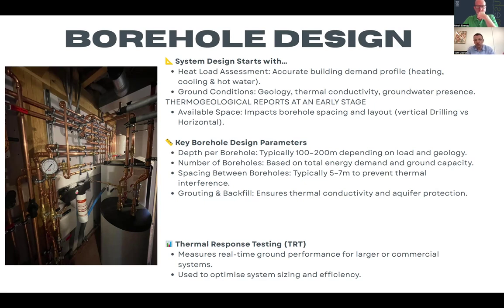That depends on the size of the project. You might drill one borehole up to 50 or more. We've been working on projects where we are looking at 300 boreholes. So it varies depending on the demand of the property. What's important is also knowing what kind of grout and backfill you are going to use in certain geology. If you've got, let's say, clay and it's dry, you would probably fill this with a grout which will expand inside the borehole to remove any air gaps and fill the borehole and provide good contact with the geology surrounding the probes to transfer the heat from the geology into the probes.